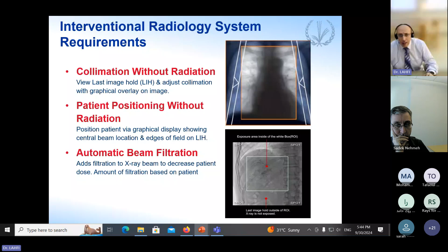Let's have a look at the room requirements for interventional radiology. In fact, the cath lab and interventional radiology room should be big enough to accommodate all the systems. So at least 55 square meters for standard interventional and up to 100 square meters for the hybrid procedure room. And we have to ensure at least 1.5 meters of clearance area around the C-arm for smooth movement during imaging. We have to consider using a modular system for walls and storage units. This allows flexibility for future upgrading. And also we have to take into account robotic assisted procedures in IR, which are becoming more common nowadays and require additional space to accommodate their accessories.